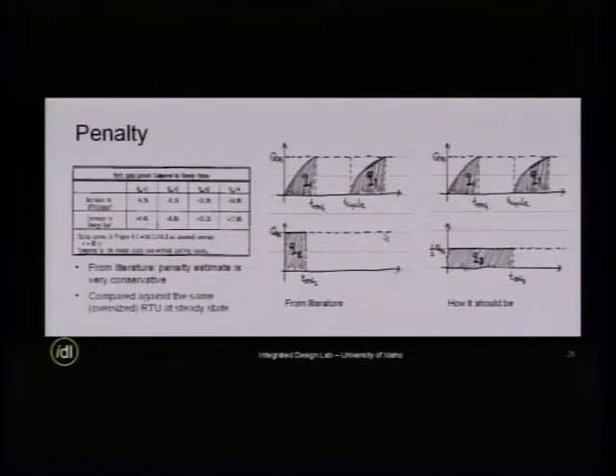Now, how about the penalty? From literature, the penalty is very conservative. If you open up literature all the way back to 1991, what they calculated is probably around a 14-15% decrease in efficiency and only 17% in energy. I would say only, because as you know, when you talk about energy savings in LEED, you're talking about 35% to get gold or even platinum. But this is only 17%.